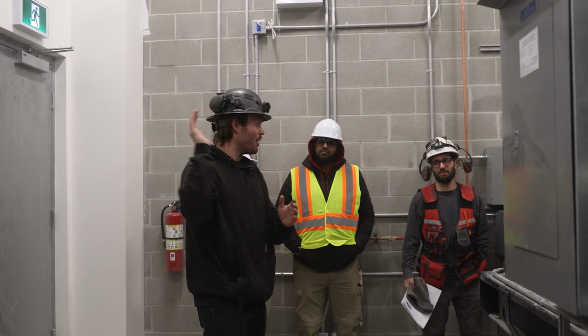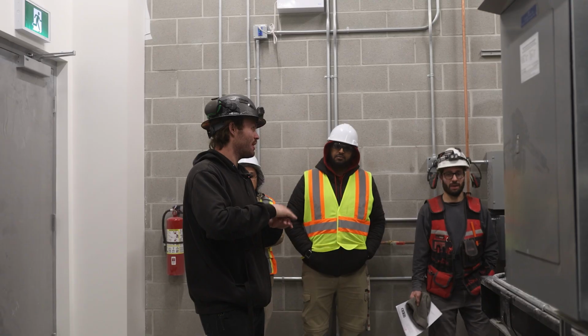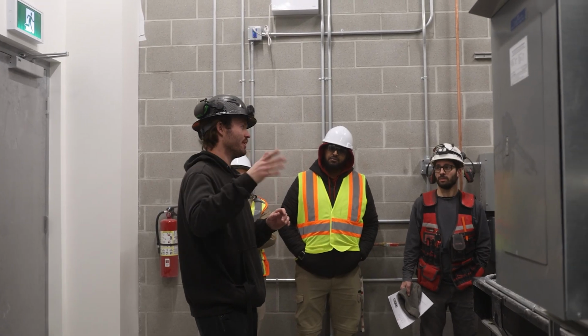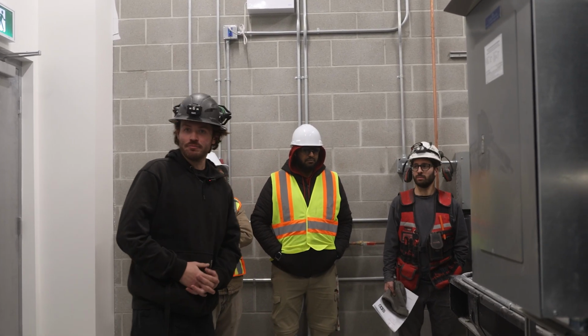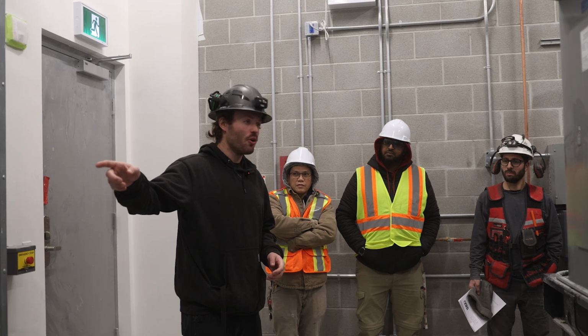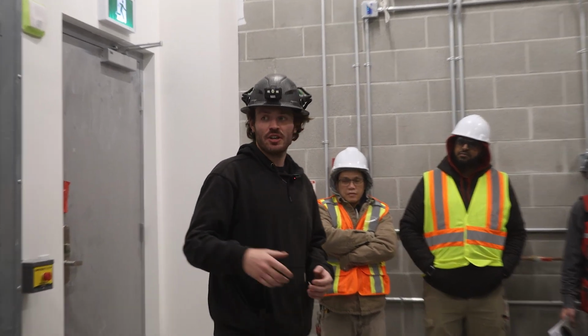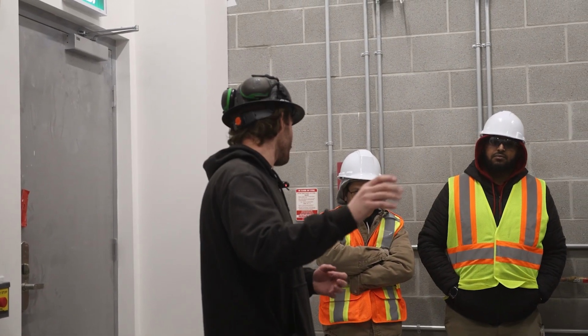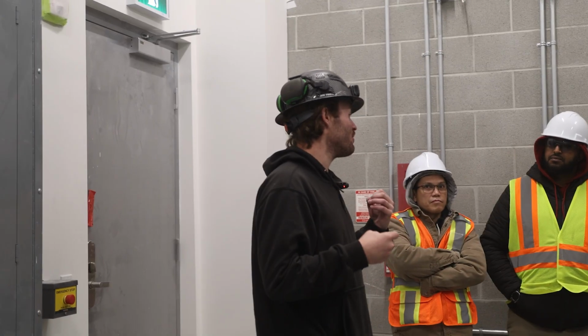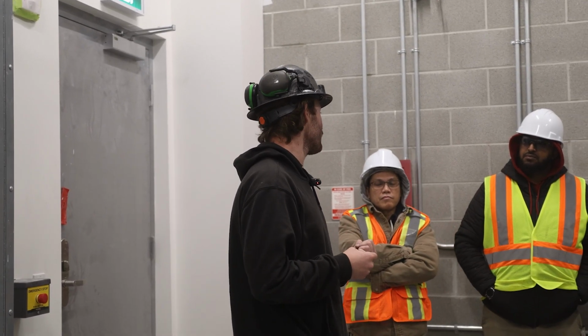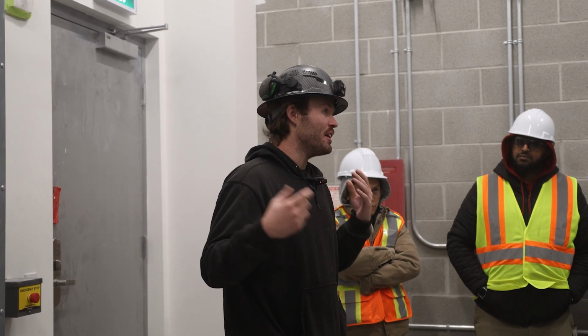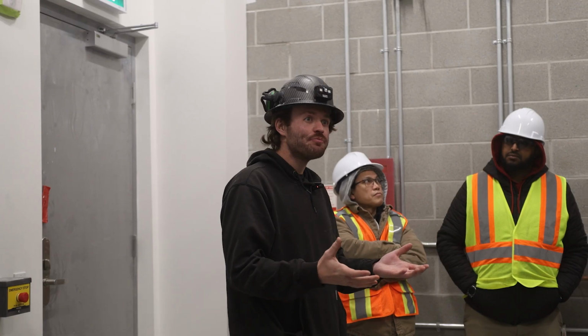It opens as soon as it starts. That can't modulate. It's got to open. I need the air in the room. So these guys will open as soon as the generator starts and start drawing air through. We need the fresh air in the room. So it's going to eventually start getting pretty cold in this room, doing it in the winter. But we need the air for the generator to run.